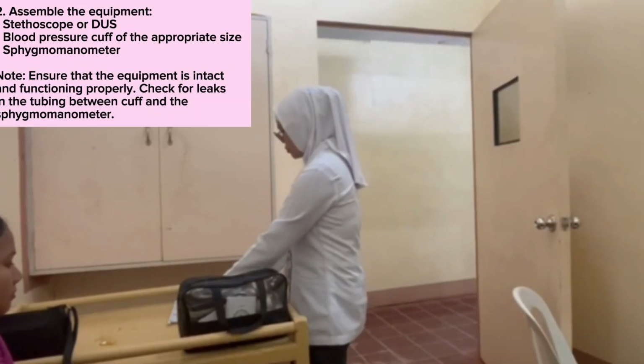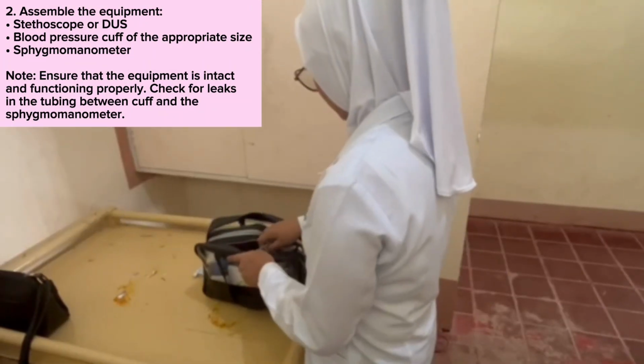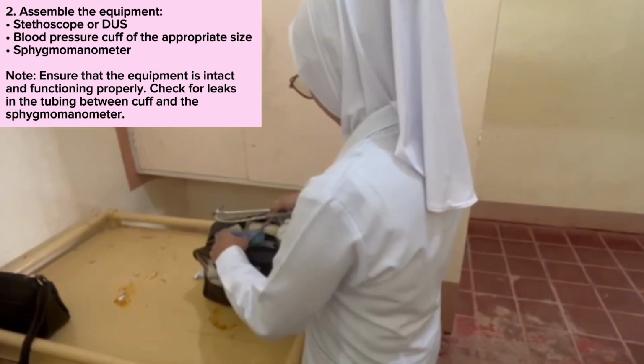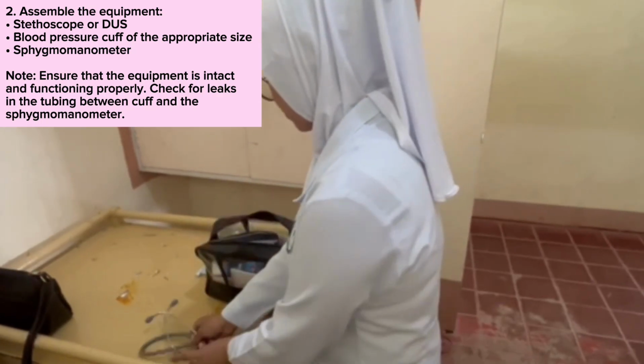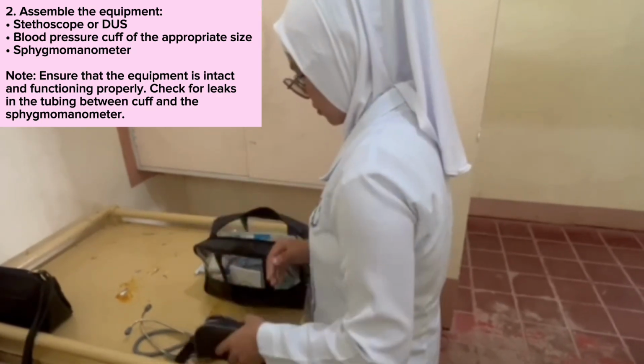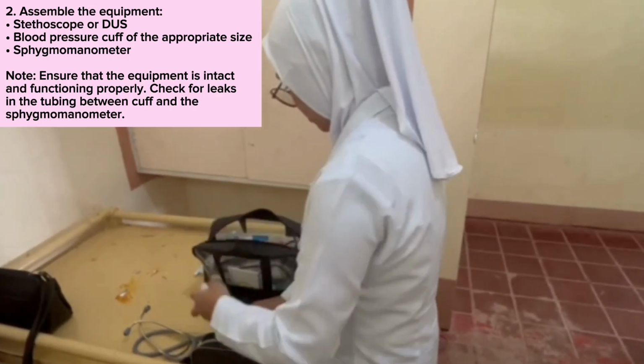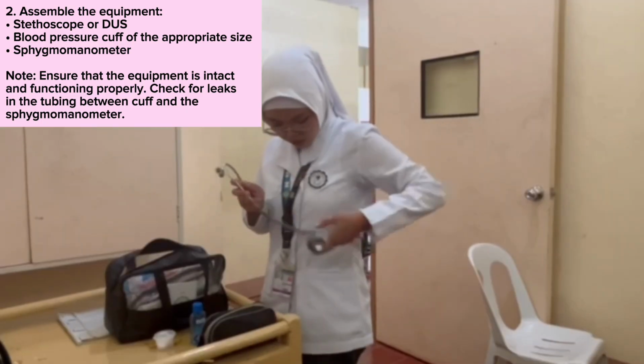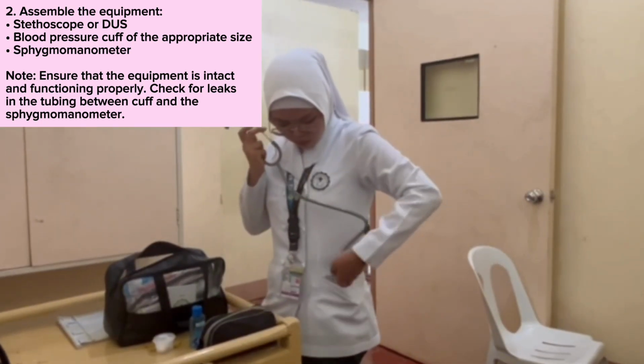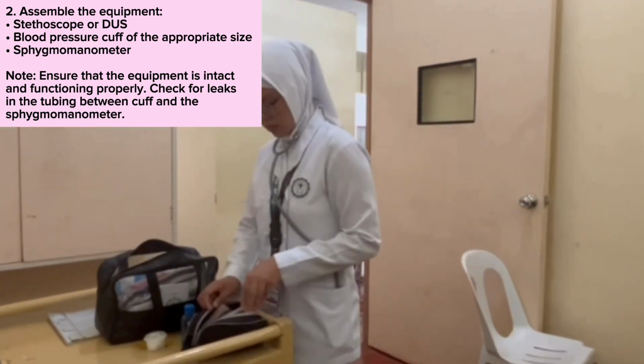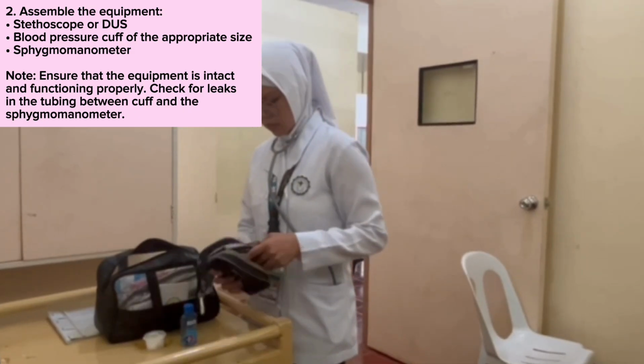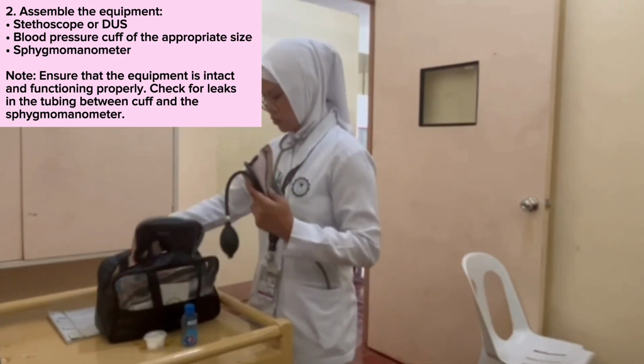Second, assemble the equipment: stethoscope or Doppler ultrasound stethoscope or DUS, blood pressure cuff of the appropriate size, sphygmomanometer. Note, ensure that the equipment is intact and functioning properly. Check for leaks in the tubing between cuff and the sphygmomanometer.